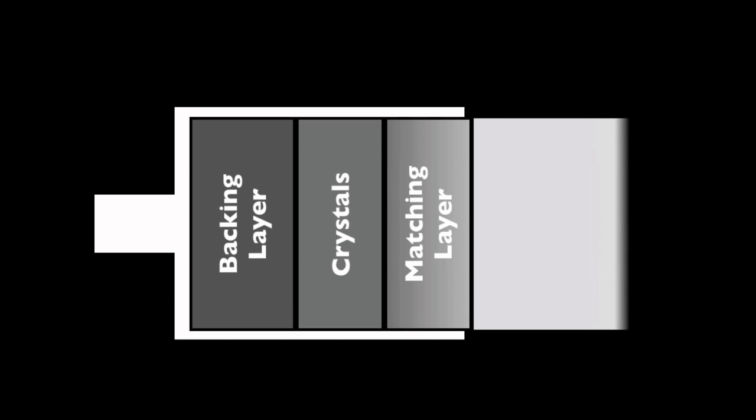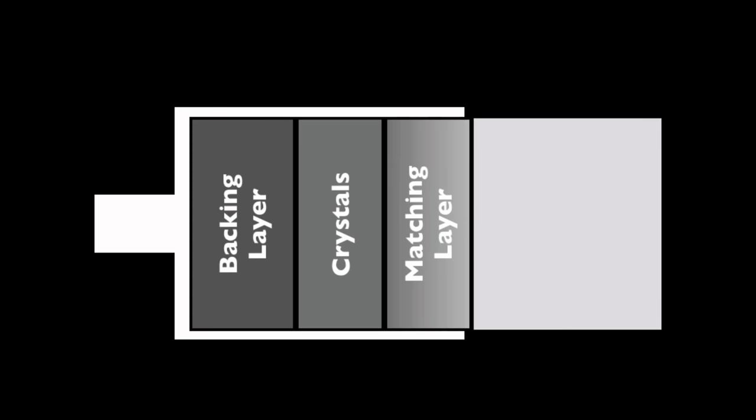The matching layer is that soft spongy layer on the surface of the probe. Electricity stimulates the crystals to produce the pressure wave, which exits through the matching layer into the subject. Broadband transducers can produce multiple different frequencies rather than a single frequency like in older systems, and you can select a different frequency.